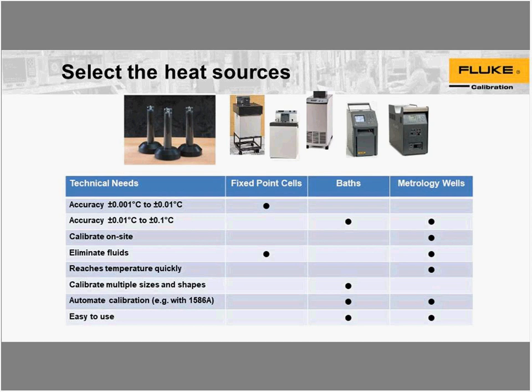Right. The next thing we need to look at are heat sources. Okay, if you need extreme accuracy, fixed point cells are going to be the way to go, and that would actually require you to use a fixed point of argon, a fixed point of mercury, and a fixed point of the RTPW, triple point of water, and then you'd still have to do a comparison at 300 degrees. Baths, you could well cover all of that except for the liquid nitrogen. We do have baths that reach down to minus 80 and all the way up to 500 degrees Celsius. You don't need quite as much accuracy, but dry wells are also a very good way to go. The only thing that they don't cover in that group would be the liquid nitrogen point.